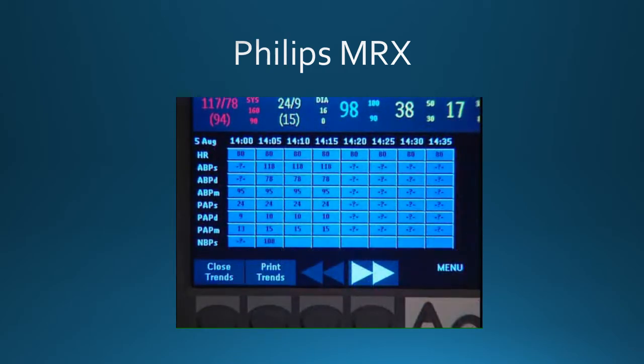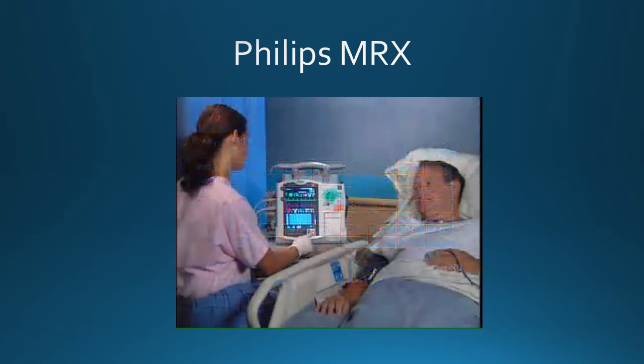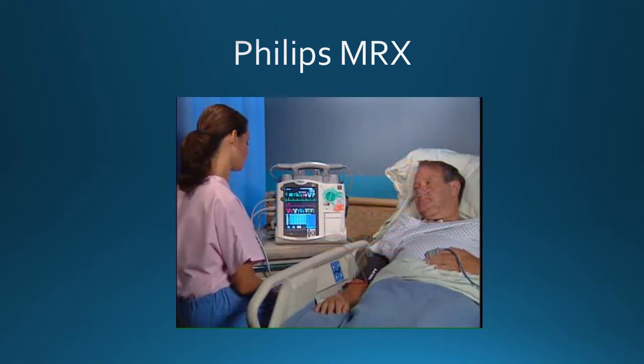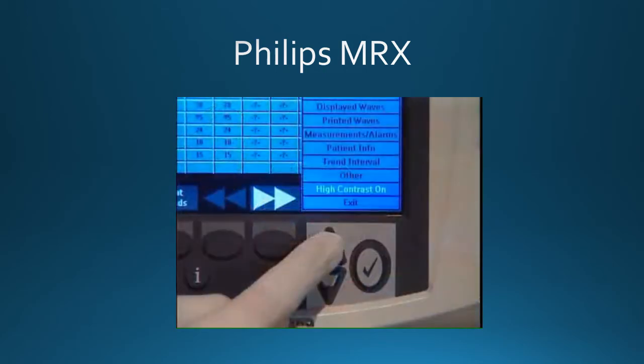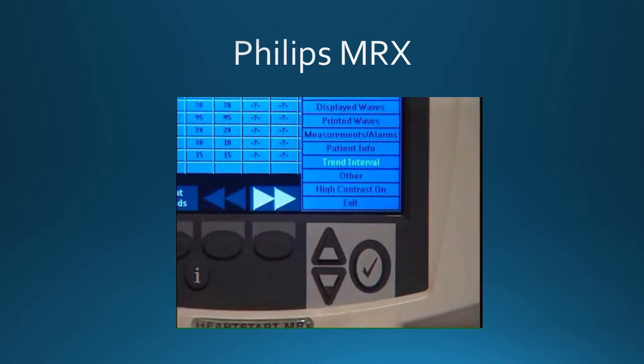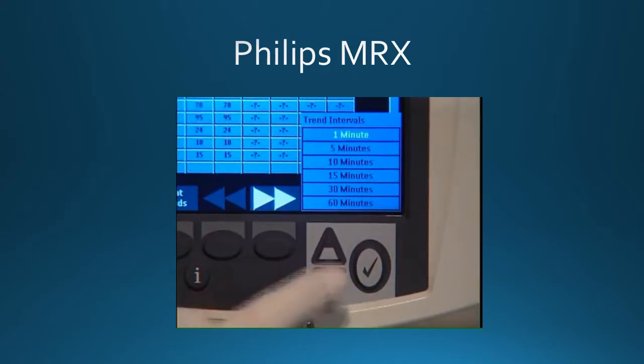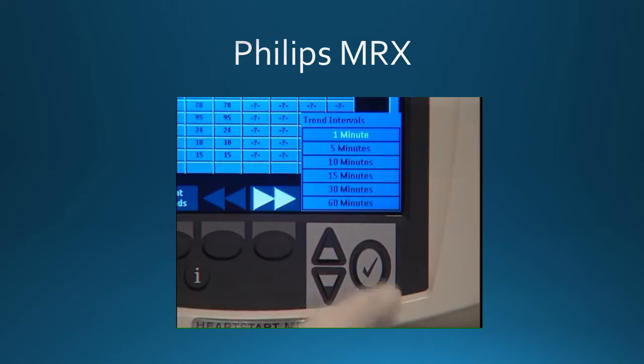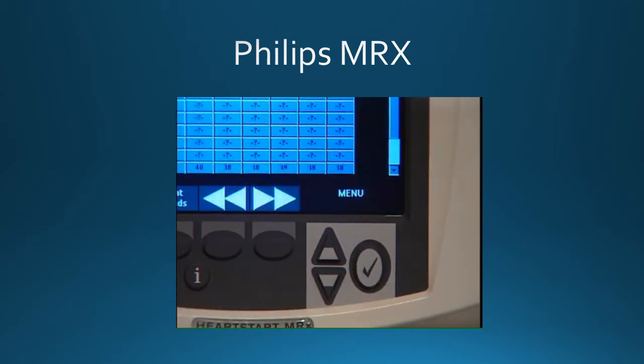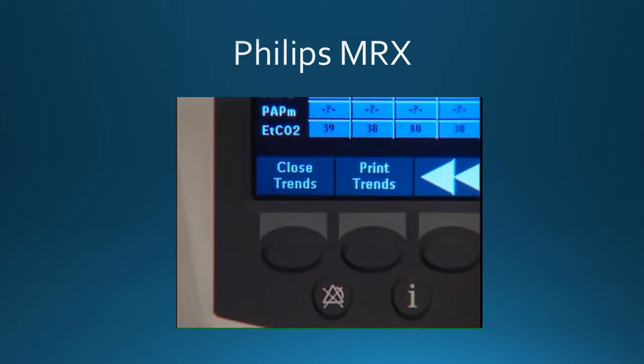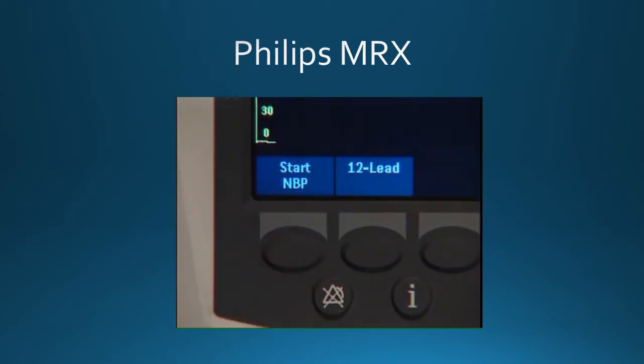You can adjust the display's time interval for the current patient. With vital signs trending active on the display, press the Menu Select button. Navigate to Trend Interval and press the Menu Select button. Use the navigation buttons to select the trend interval you want and press the Menu Select button. To exit the trending report, press the Close Trends soft key.